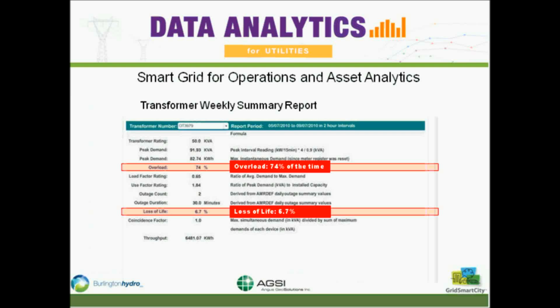I think one of the things coming up - Dan and I have been talking about this - there's a pretty big smart grid project starting in Ontario. We're working with Siemens, and we're going to be putting sensors on the transformers to get more information like oil temperature, and running that against manufacturer data to try to come up with a much more accurate calculation. But given where we were with the meter data, and there were no meters or sensors on the transformers, it was the industry standard one we used.